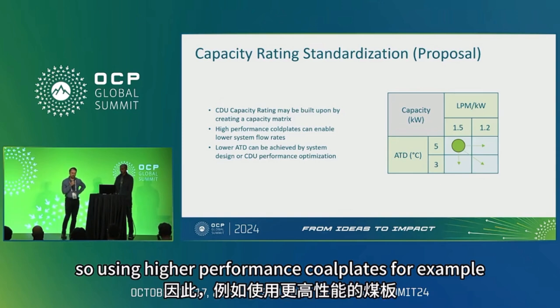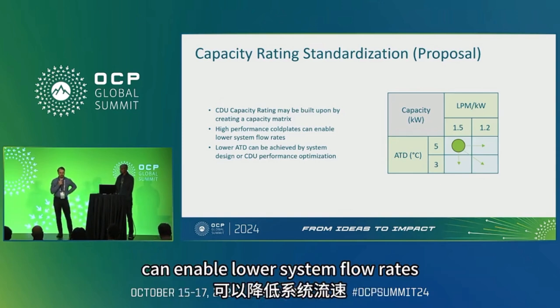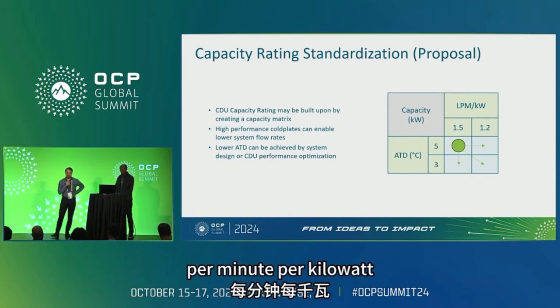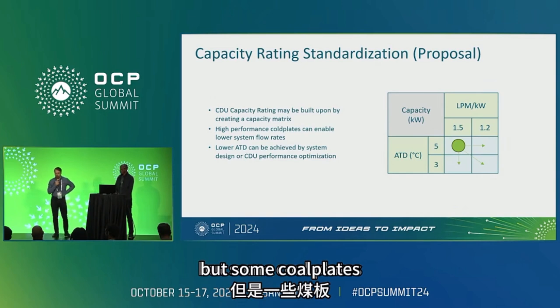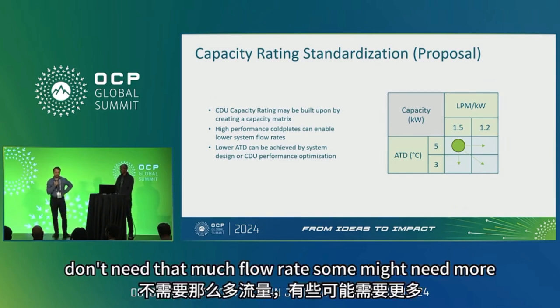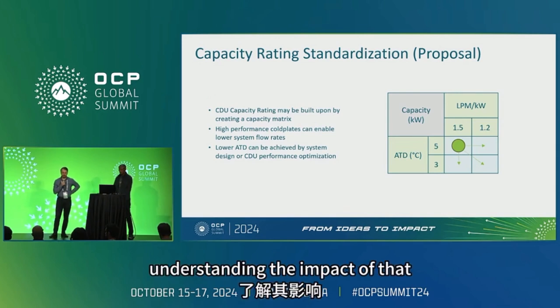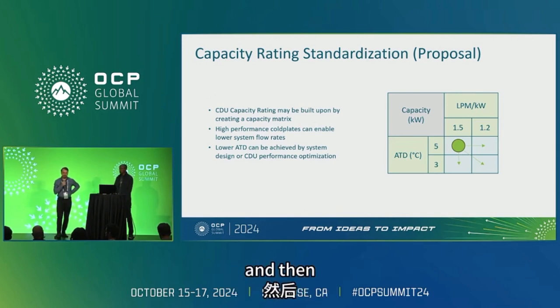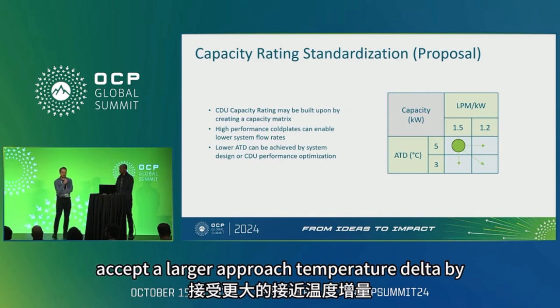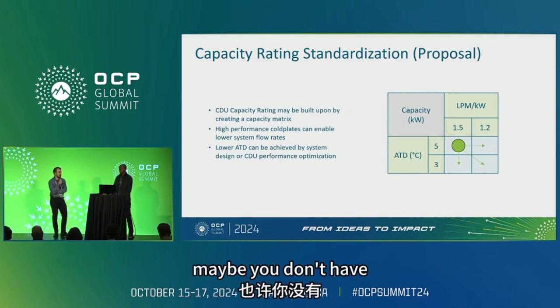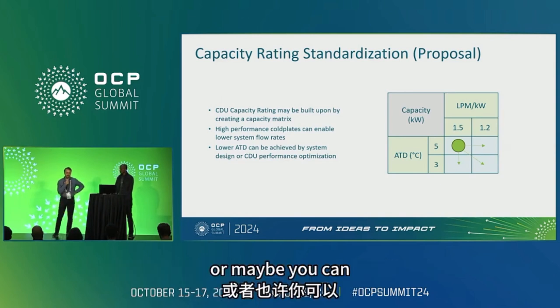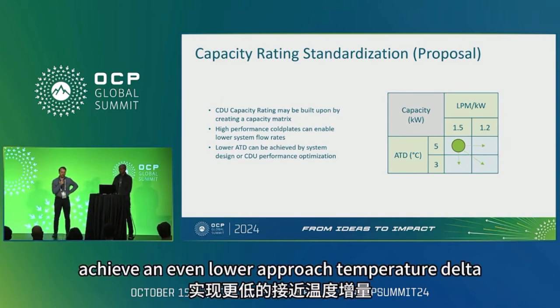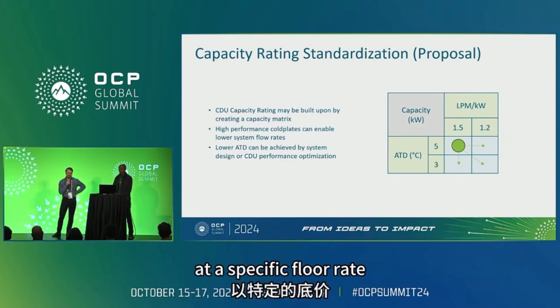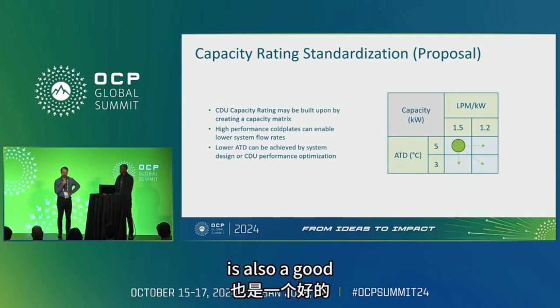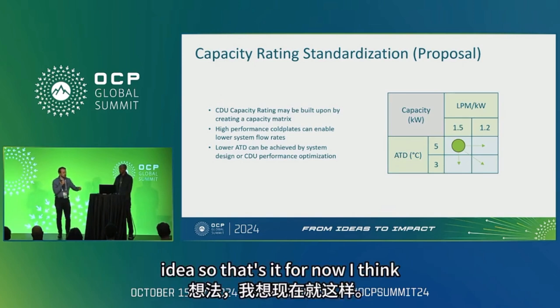So using higher performance cold plates, for example, can enable lower system flow rates. We used 1.5 liter per minute per kilowatt as kind of a standard starting point, but some cold plates don't need that much flow rate. Some might need more. And so understanding the impact of that on the system is important. And then for the approach temperature delta, you may be able to either accept a larger approach temperature delta by your system design. Maybe you don't have such strict requirements on the facility side, or maybe you can design your CDU to achieve an even lower approach temperature delta at a specific flow rate. And so showing that in a bit of a matrix format is also a good idea. So that's it for now.